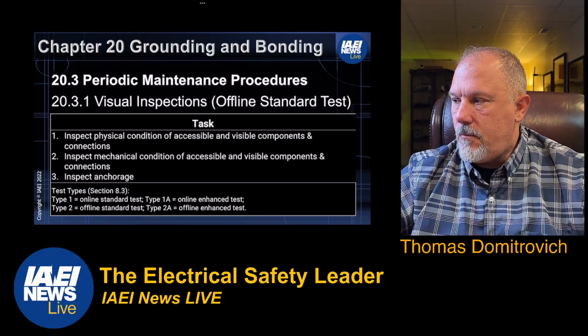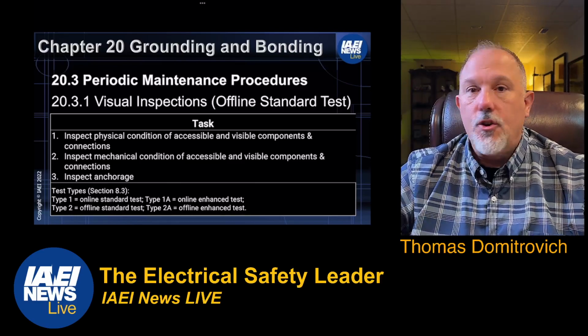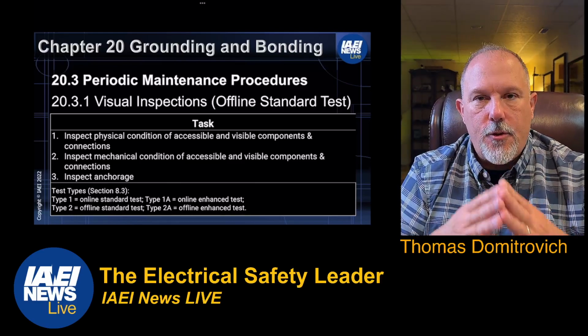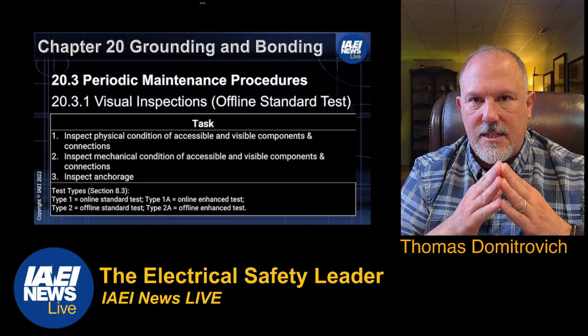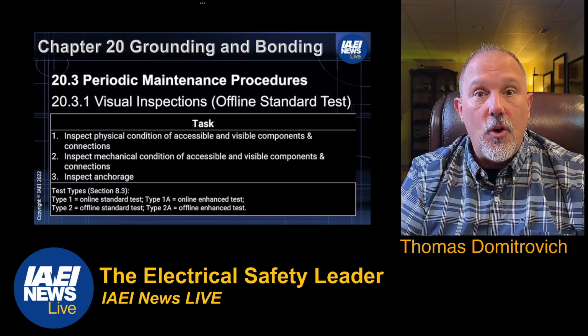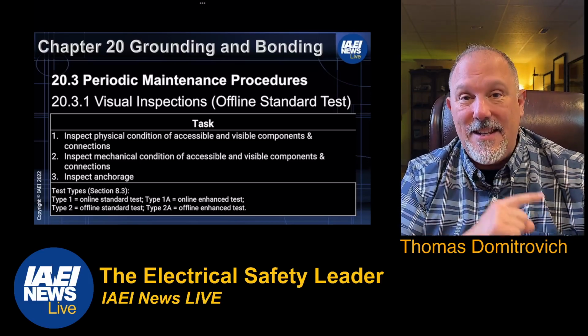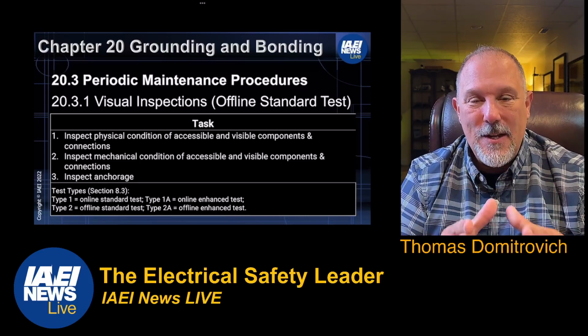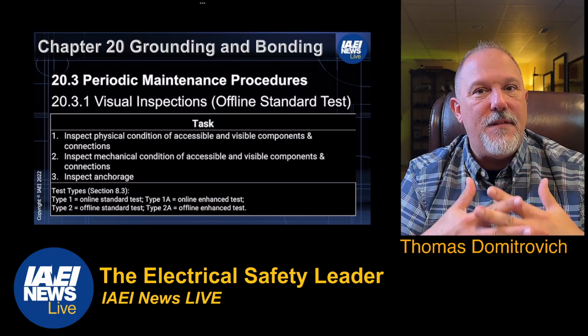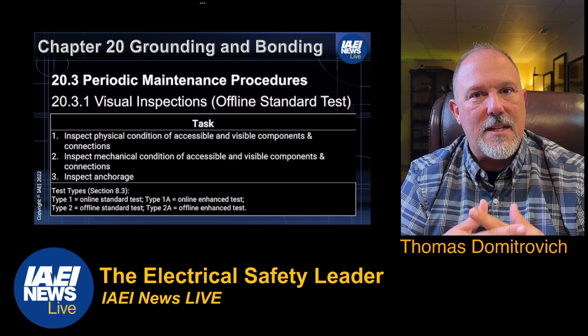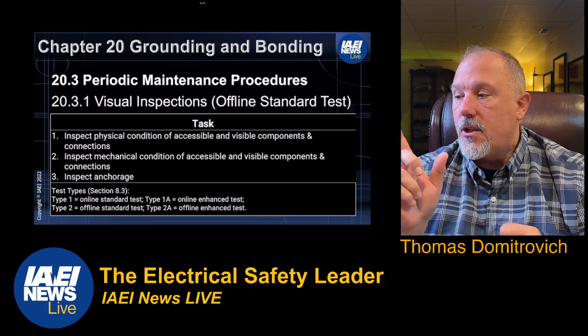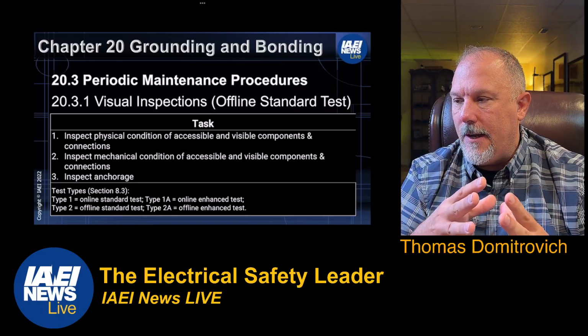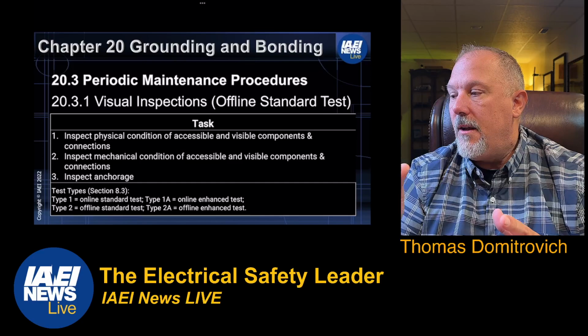So these are offline - you're going to be inside that equipment. You're going to have to establish an electrically safe work condition following NFPA 70E. Again, you see the dovetail of these documents and how they relate to each other. So you're going to look at the door, and they said accessible and visible.